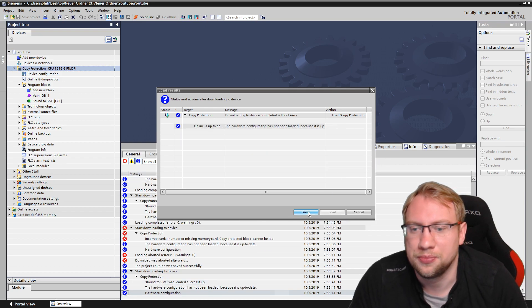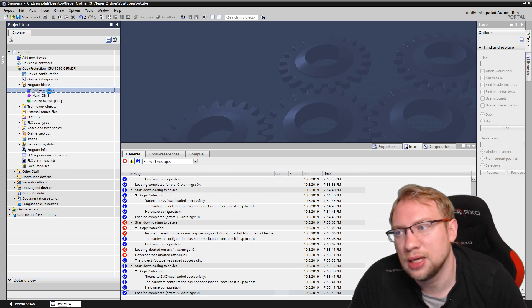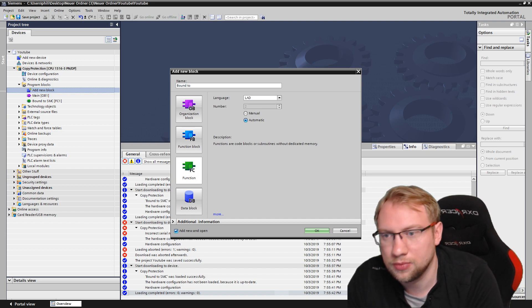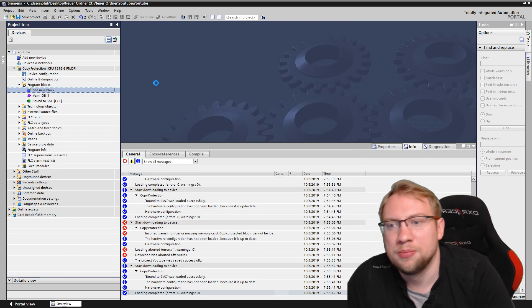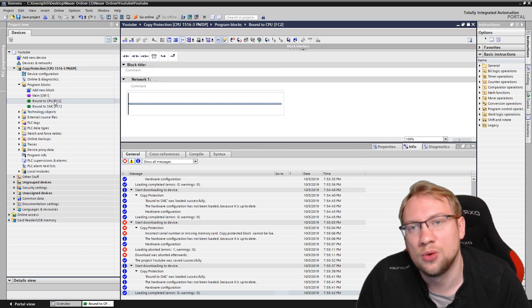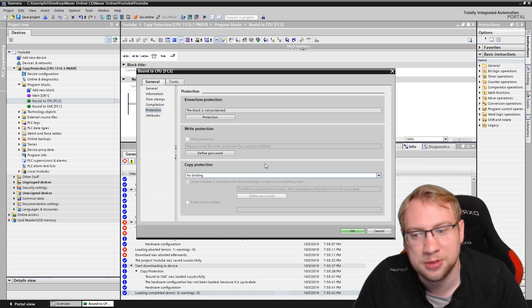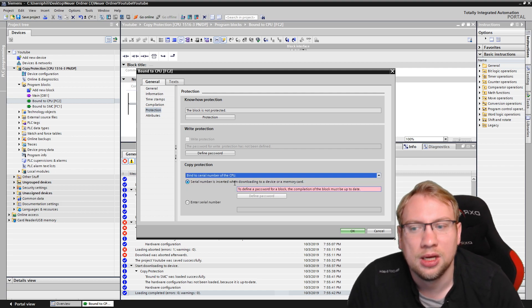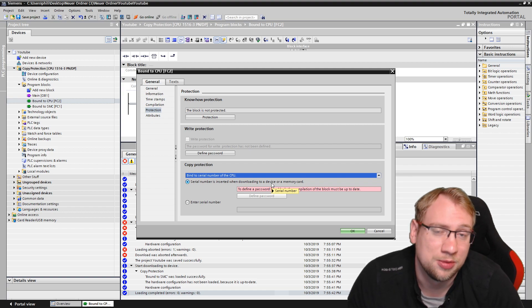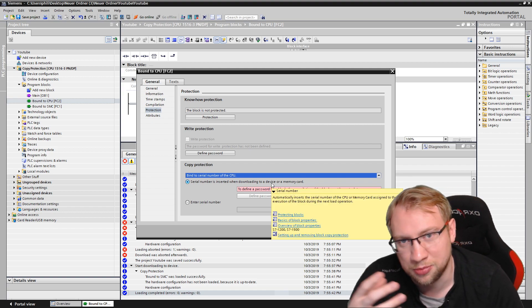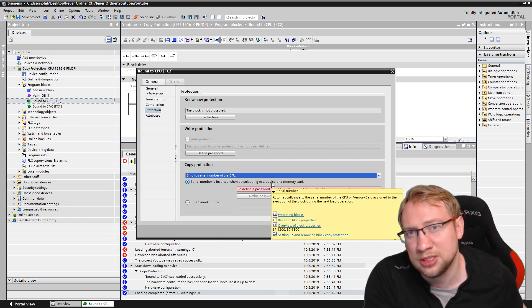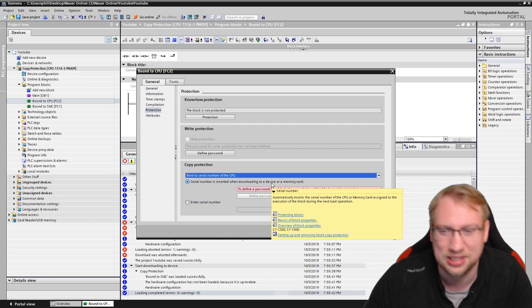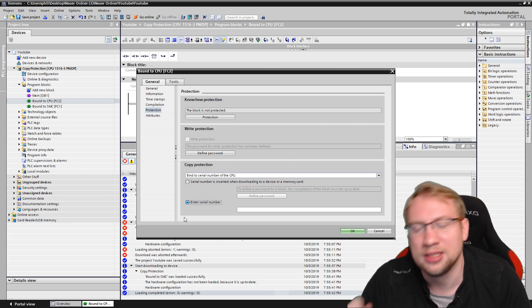The next option — actually more important to me — is binding the program to a CPU instead of a memory card. I can bind the program to a specific CPU, so it can only be downloaded to that one CPU. The process is the same: it will ask for a password when downloading. Everyone with access to the PLC can copy the program, but they cannot run it anywhere else — they can copy it but can't do anything with it.